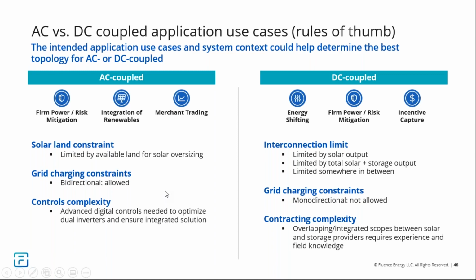There are two more complexities, one for each AC and DC coupled. To truly capture the optimized value of an AC coupled system, you need advanced digital controls that can control the dual inverters together and ensure you're truly integrating those solutions for maximum value. So when procuring these systems, it's important to consider what your power plant controller looks like, and that it's experienced and tested in the field.